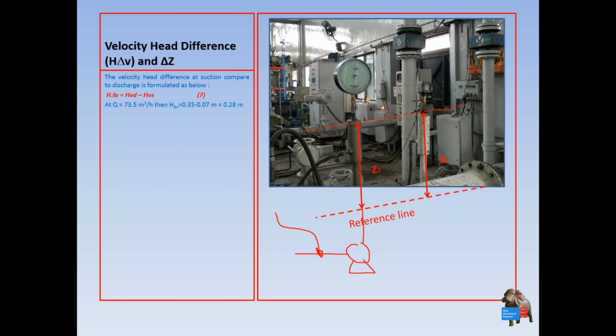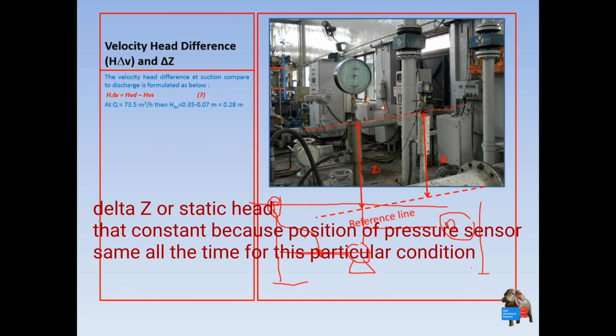pressure transducer to read the suction pressure, and here a pressure transducer to read the discharge pressure. You have to understand the difference in height between these two, how much is the difference? Because we want to know the testing points of this rig, so that will be delta z.